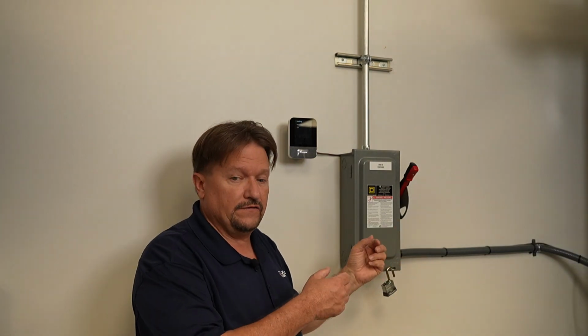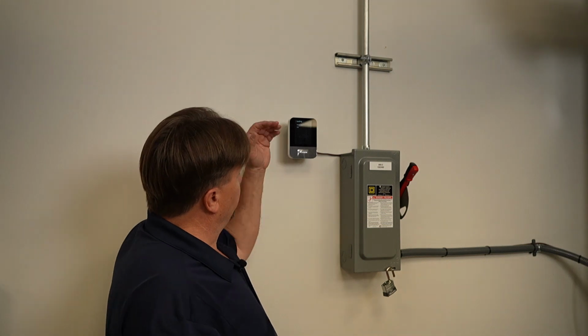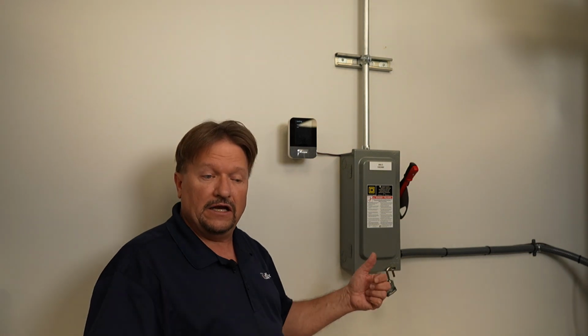Now, it's going to take a minute because this is an inverter. It has a compressor that will not hurt itself, so it's going to have a little bit of time, just like our older units, our standard units. It's going to have a delay. Once it cuts on, it's going to run, and I can go in there and test everything. If I've got my D-checker hooked up, my superheat is going to be at 9. It is going to be 9 degrees. So I'm looking for 9 degrees superheat, and if it isn't, then maybe I have something wrong with my EEV.